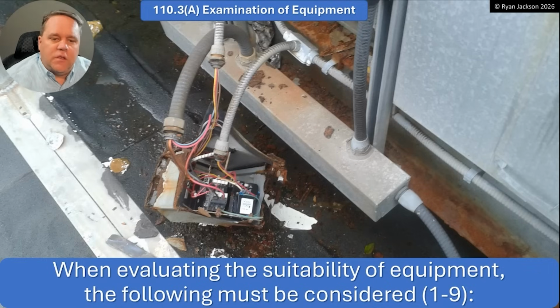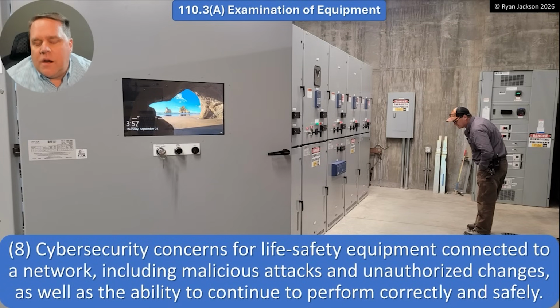Looking at this picture here, I think it's clear that at least one of the items in 110.3a, 1 through 9, was not satisfied - that would be corrosion protection. Obviously, that is not suitable for that application. Now, item 8 was added in the 2023 code to address cybersecurity concerns, which is kind of a funny change, because that's certainly not something our grandparents were talking about when they were working with the National Electrical Code.